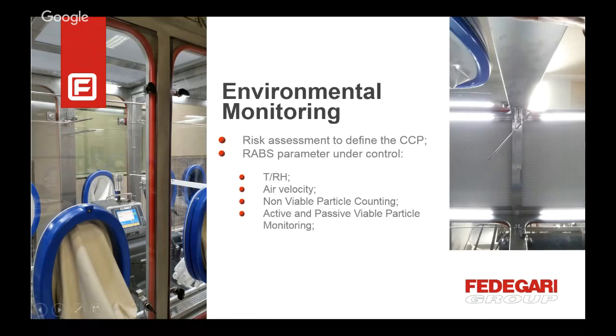We are checking the air velocity. Here you can see an air velocity probe, a hot wire air velocity probe, in order to be sure that the unidirectional airflow is working properly. Then we have non-viable particle counting. In this case, during a validation, we have an independent particle counter, but we have probes in the critical control points, and also active and passive viable particle monitoring. So all the parameters that are required to classify and to validate a clean room and the unidirectional flow are in position.